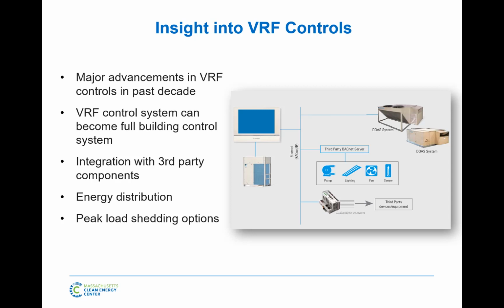So what it can do with energy distribution software is, if you plug in some power meters so you can calculate how much electricity the central units are using, and you wire that and tell that to the central controller, it'll distribute that for you. It'll run an algorithm every 20 seconds to figure out where all the expansion valves are, and it'll say, okay, in the past hour, condenser unit A, you used 10 kilowatt hours. I'm making up numbers. Fan coil A, you're responsible for 1.2 kilowatt hours. Fan coil B, you're responsible for 1.6. Fan coil C, 0.8. Fan coil D, and so on and so forth.